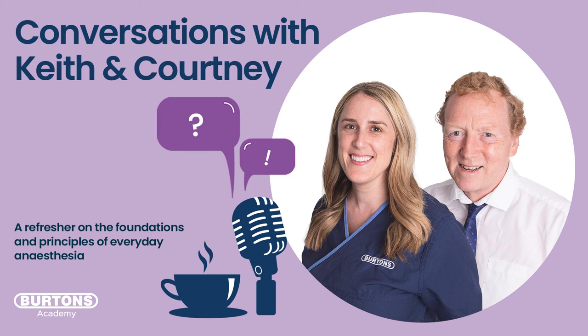With Doppler, you get a good indication of systolic pressure. The point of maximum intensity — the loudest point of the Doppler noise — could be associated with mean arterial pressure, but the science is a bit vague, and one person's assessment of maximum intensity isn't necessarily the same as another's. Diastolic isn't going to give you any useful reading. So Doppler is a nice system, easy to use, gives good feedback because you can hear it, but you're really only going to get a systolic value.